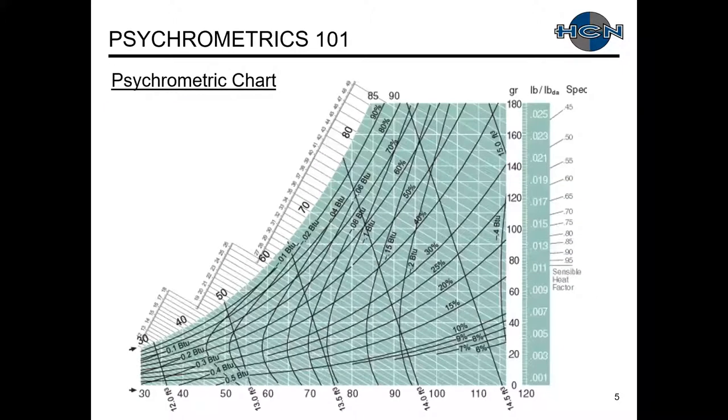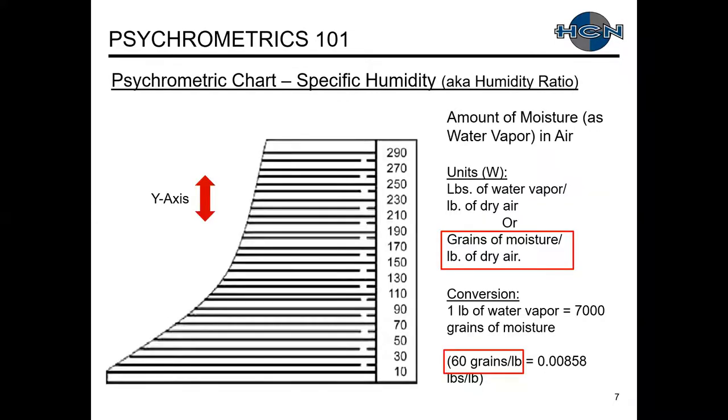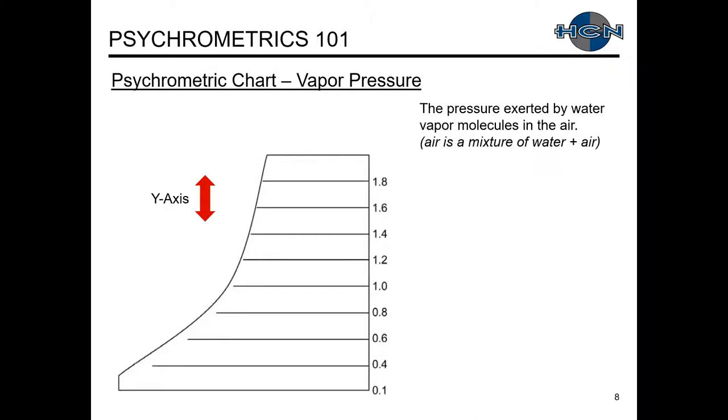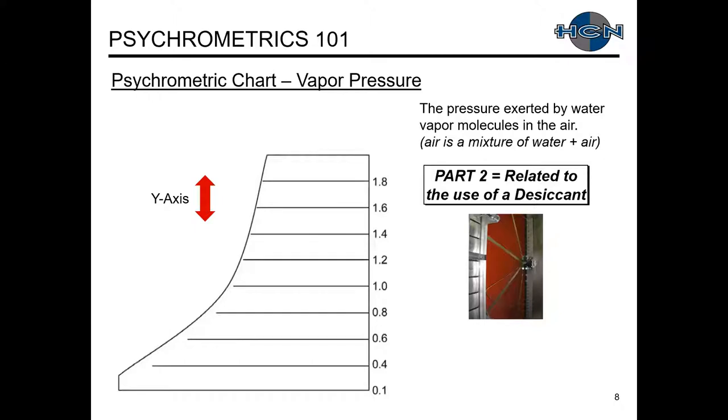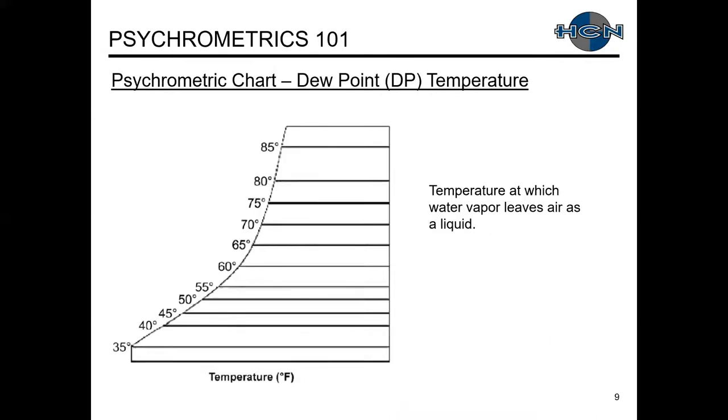A partial review of psychrometrics — going through these quickly since it's a repeat from Part 1. Here's our psychrometric chart. Dry bulb temperature on the x-axis — everybody's familiar with that. On the y-axis is the amount of moisture as water vapor in the air, also called specific humidity or humidity ratio, measured in grains of moisture per pound of dry air. Next is vapor pressure — the pressure exerted by the water vapor molecules in the air. Moisture travels on the psych chart from higher vapor pressure to lower vapor pressure. Dew point temperature is the temperature at which water vapor leaves air as a liquid, shown on the left on the saturation line.